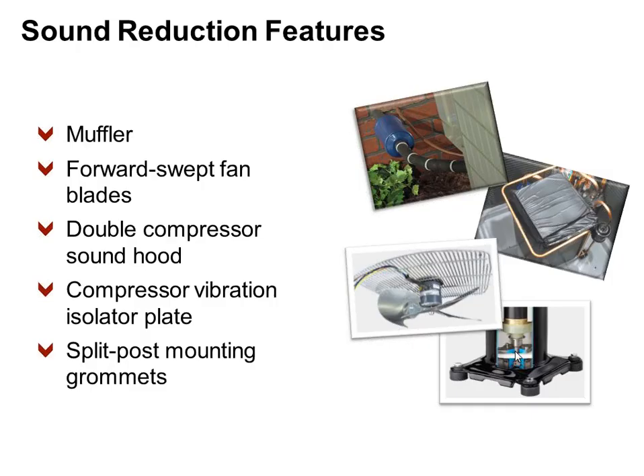Some of the things that make this unit so quiet: it has an internal muffler system on it. It also has an external muffler that ships with it. You can see that up in the top right there, the little brick wall that muffles some of that sound. It's kind of like a silencer on the barrel of a gun. The fan blades are shaped in such a way that they reduce sound. We do this on some of the other Bryant and Carrier high-end condensing units anyway, so that's already built in. But it's what we call a forward swept blade. And I'm told that the guys at the Sikorsky Helicopter Group helped the Carrier guys design this. So I don't know if that's impressive to you or not, but apparently they know about airflow.